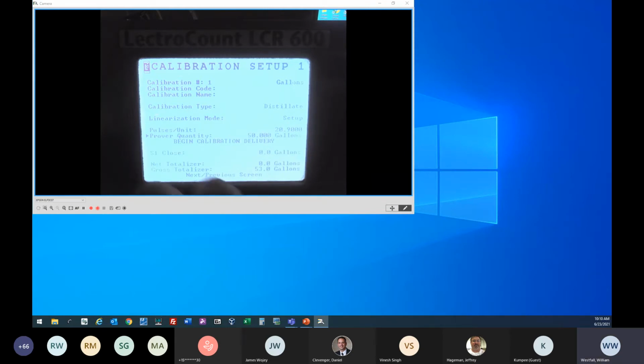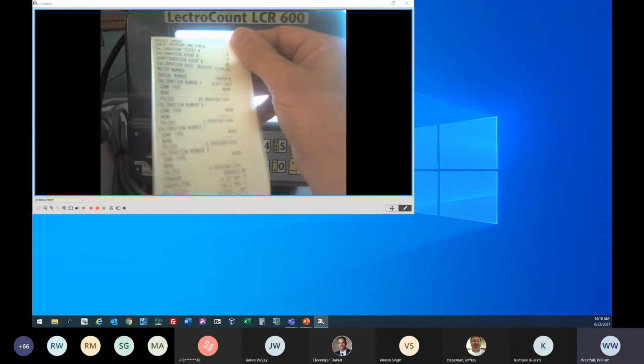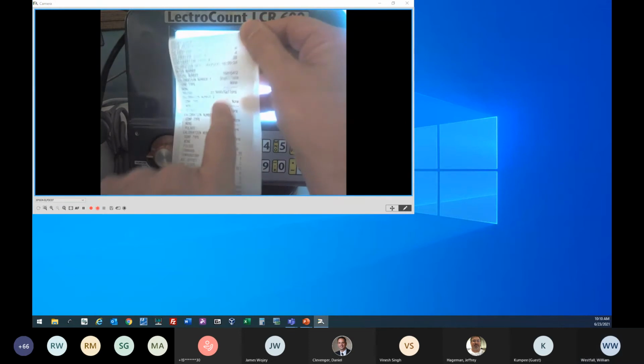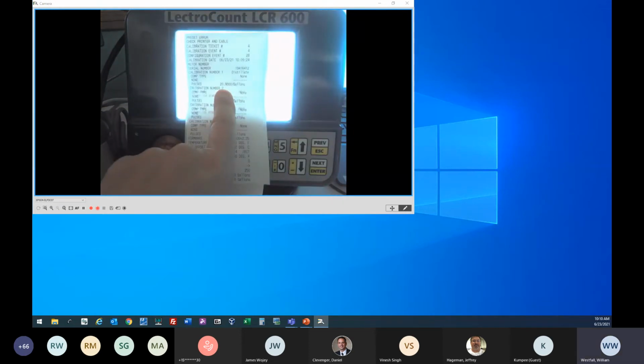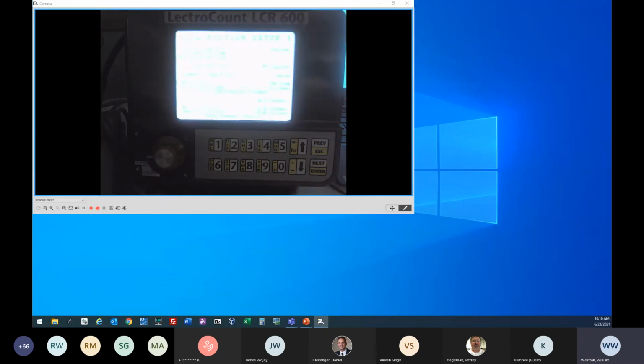Okay, now if we take our red knob and come back out of calibration into the stop position, you can see the red knob now is in our stop position here. And if we look at our calibration ticket here, there's our new calibration ticket. So you can see now we've got the 2090, or 20.90, in there. So now we've actually gone ahead and calibrated that meter. So again, it's pretty simple on an LCR 600.